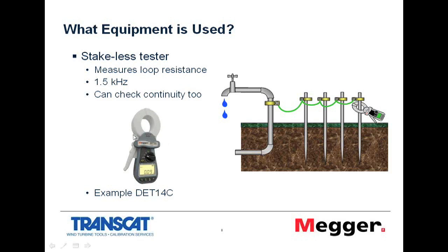In this head there are 2 cores. One core is inducing the current, and the voltage on that coil is kept constant. Therefore, the amount of current being induced is inversely proportional to the resistance of a loop. And you can see here, I've placed the instrument around this particular electrode, and what I will be measuring is this electrode in series with all these other earth paths in parallel. And basically, it's a loop tester, so it's important that you understand where the current is being injected.